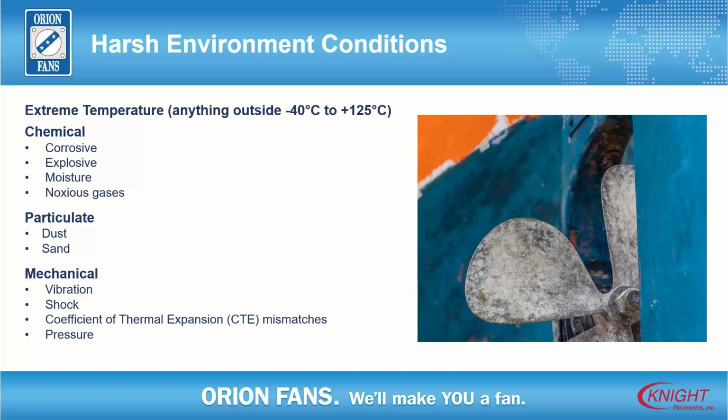Dust, dirt, and sand. Those are very hard because some of the sands, depending on where they are, can be quite conductive, and that can be a problem. One of the problems we had, a customer was building car washes in Saudi Arabia, and he couldn't keep the fans alive. So we built him an IP55 fan and made the problem go away. As far as I know, we've had zero failures since we switched him over to an IP55 version fan.